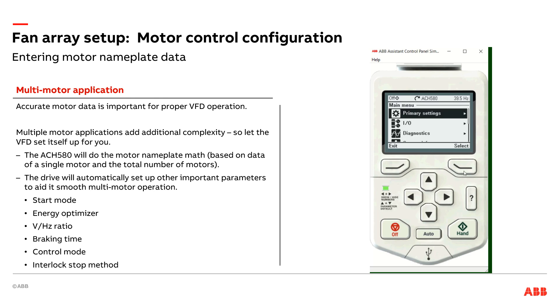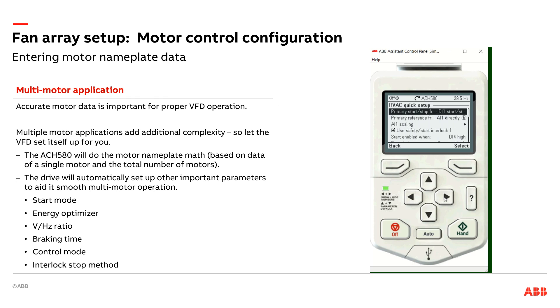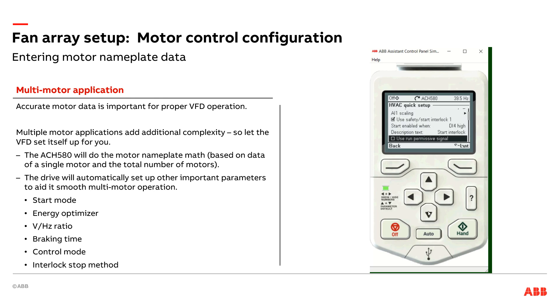I'm going to come into the menu, go to Primary Settings, Set Select. I'm going to go to HVAC Quick Setup — if you've seen enough of my videos you know I love working in the HVAC Quick Setup — it covers most of my needs right in here. I'm going to scroll down to Motor Nominal Values because that's where I enter my motor data.